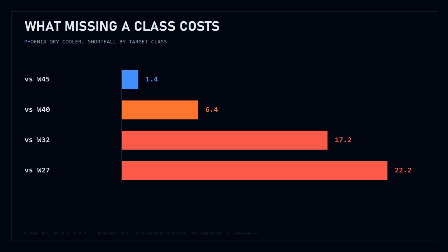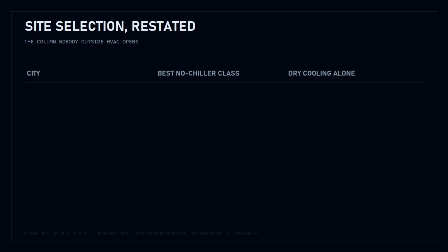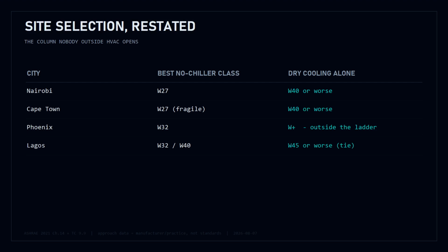And it changes site selection in a way the announcements never mention. A city can have cheap land, good fiber, and a grid connection, and still be the wrong place because of a column in a table almost nobody outside HVAC opens. Phoenix is not a bad place for a data center. It is a bad place for a dry one.